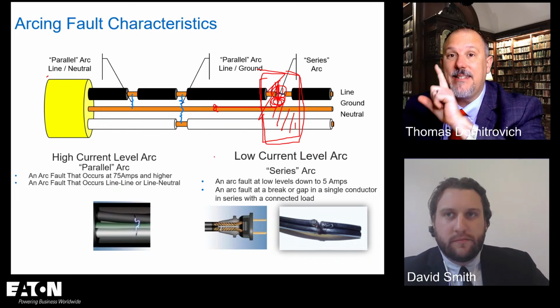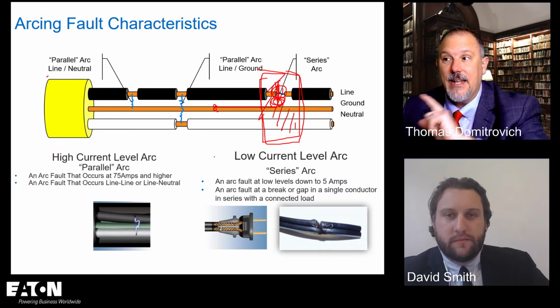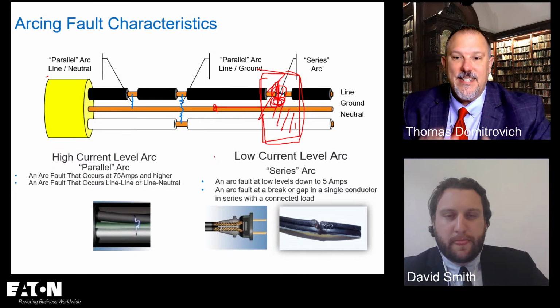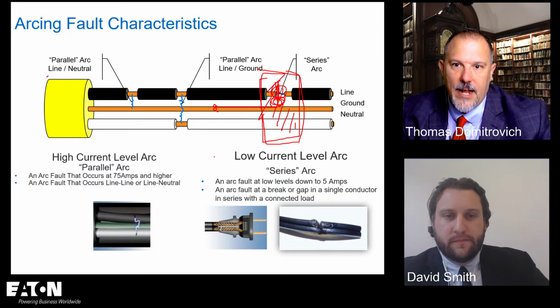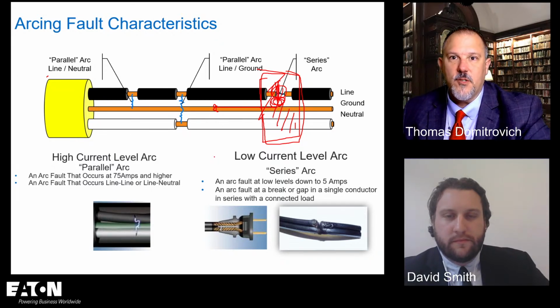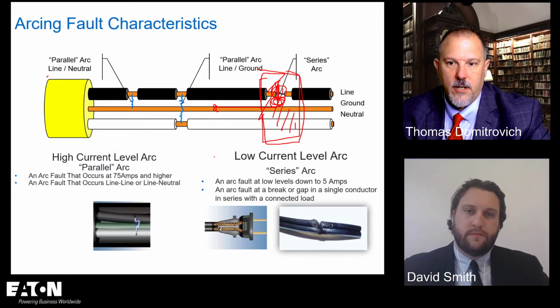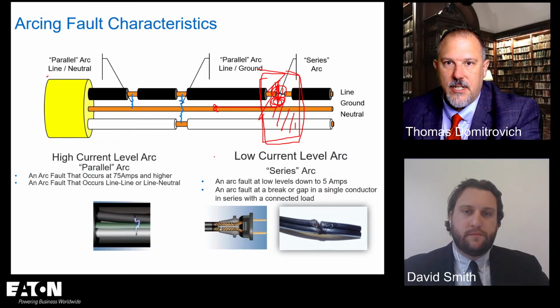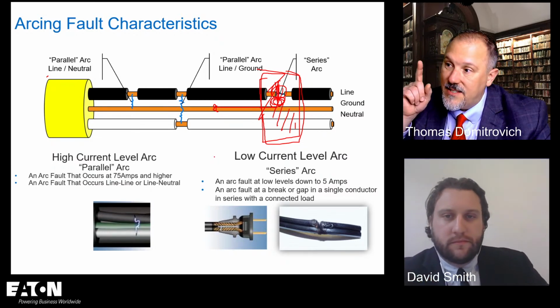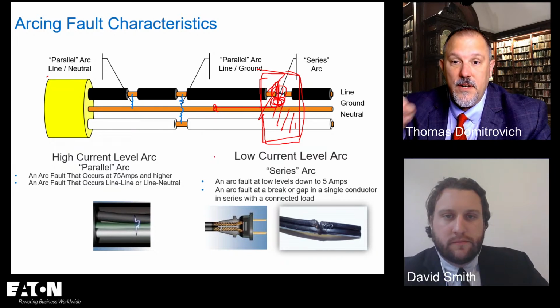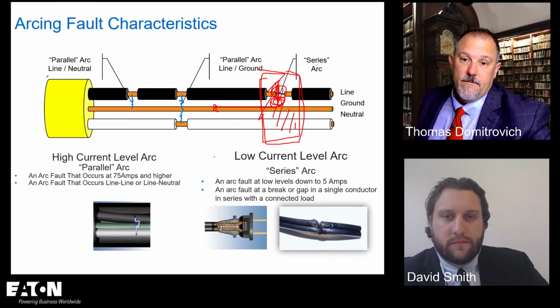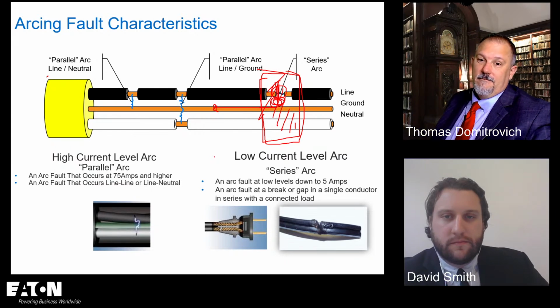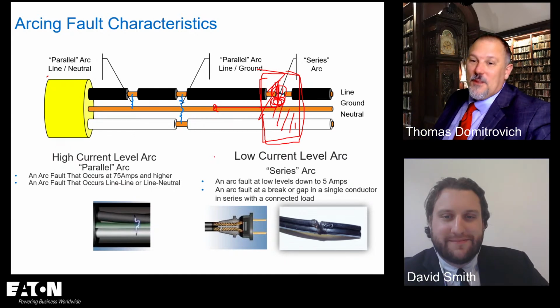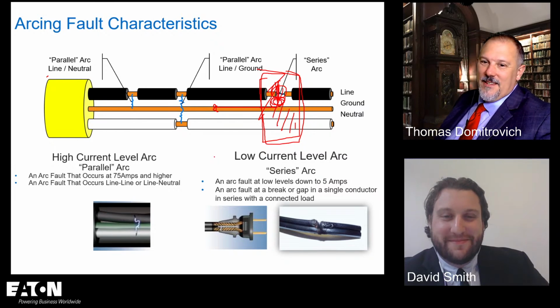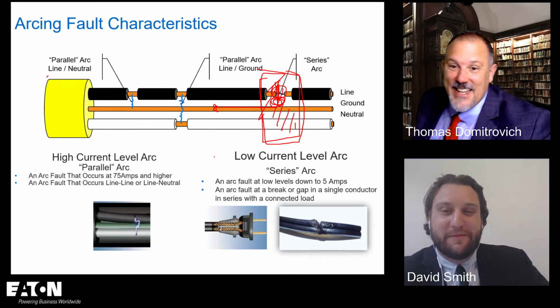And it will detect a series arc in NM wire. So if we said the difference between a branch feeder and a combination type AFCI was that a branch feeder did parallel arcs and a combination type did series arcs, that would be wrong, because this test for a branch feeder AFCI is a series arc test. What do you think? It's a lot. It's a lot to take in.